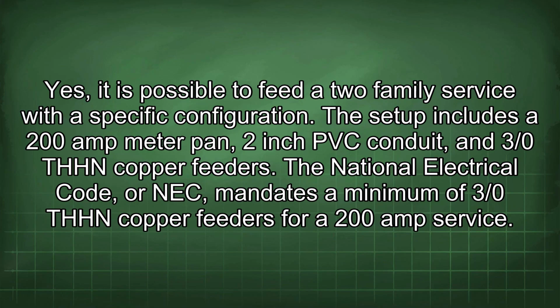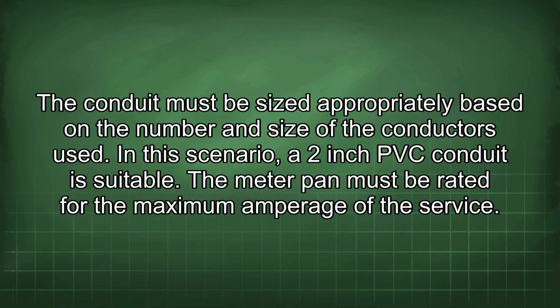Yes, it is possible to feed a two-family service with a specific configuration. This setup includes a 200 amp meter pan, 2-inch PVC conduit, and 3/0 THHN copper feeders. The National Electrical Code, or NEC, mandates a minimum of 3/0 THHN copper feeders for a 200 amp service. The conduit must be sized appropriately based on the number and size of the conductors used. In this scenario, a 2-inch PVC conduit is suitable. The meter pan must be rated for the maximum amperage of the service.